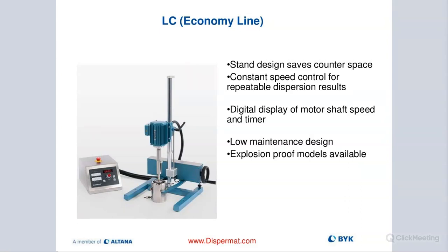So we also have a budget model, which is called the LC line, which is a really nice small lab unit. Again, the same motor technology. These are brushless step motors, ultra quiet. You can hardly hear them, hardly any vibration. Just a standard small lab unit, giving you the speed as well as a timer on the display of our control box.